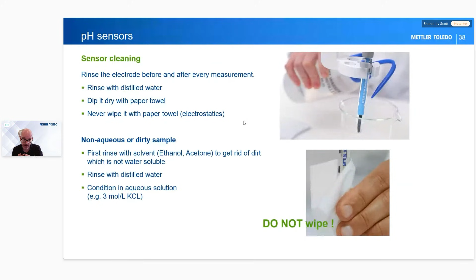Before we take our first measurement, we need to do calibration and adjustment. We must calibrate our pH meters at least once a day. It may, yet again, be down to your SOP. If you're using your pH meter every day, you should calibrate it. If you use it once a week, then you should calibrate it before you start using it. If you have regulations or SOPs where you must calibrate after every batch, then obviously you need to do it after every batch. We should be performing at least a 2-point calibration.